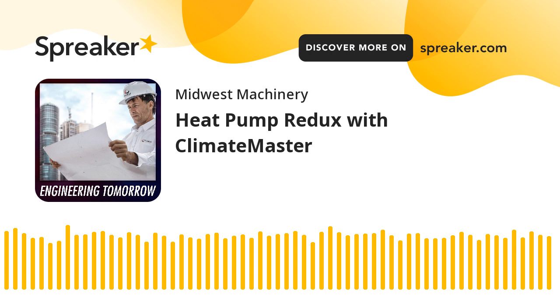Well, another variation that we can do is that we can actually combine a geothermal and a traditional water source heat pump system. And some of the reasons why we may want to do this is, if you think about it, one of the disadvantages of a geothermal heat pump system is the upfront installation cost and the size of that geo field. That field can be extremely large and it can be extremely expensive to size depending on the size of your building. If you have a very large building, you're going to have a very large field, and that installation is going to increase significantly.